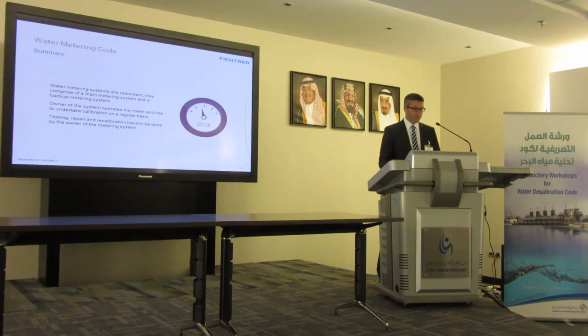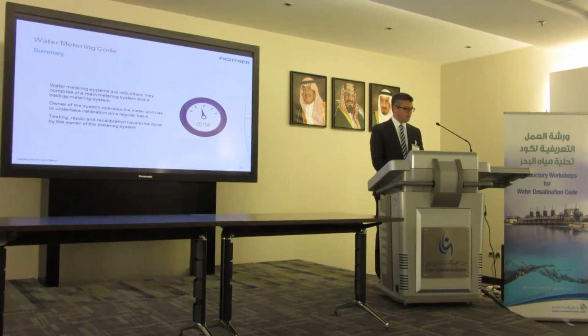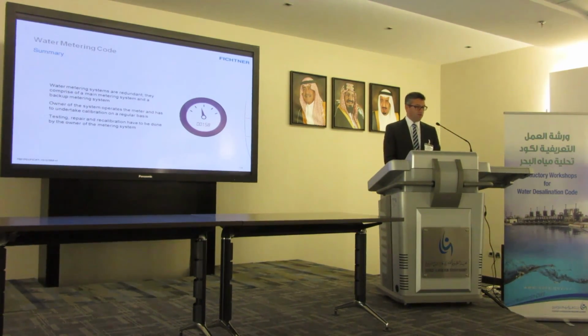In summary, water metering systems are redundant. They comprise a main metering system and a backup metering system. The owner of each of the systems operates the meter, and they have to do the calibration on a regular basis, and also the testing, repair, and recalibration have to be done by the owner of the metering system.